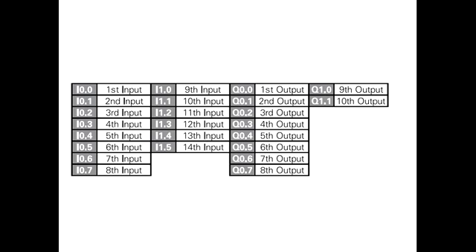I designates a discrete input and Q designates a discrete output. The first number identifies the byte, the second number identifies the bit. Input I0.0, for example, is byte 0, bit 0. The following table identifies the input and output designations.